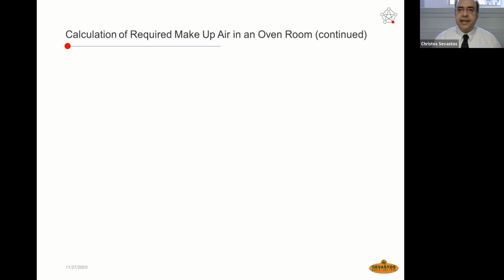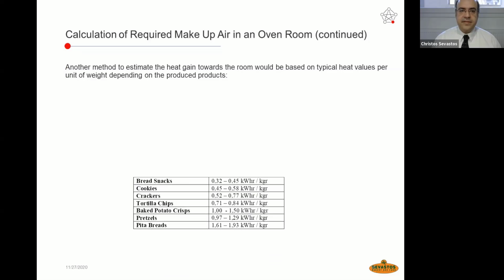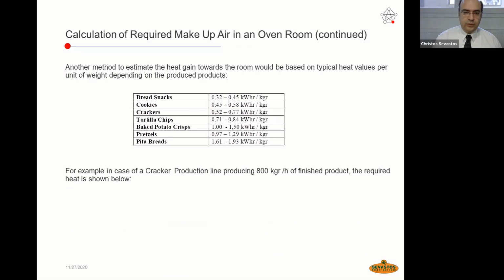Calculation of required makeup air in an oven room. Another method, instead of using the previous method, with which we can estimate the heat gain towards the room would be based on typical heat values coming from the heat rate per mass, which is required for several kinds of products.